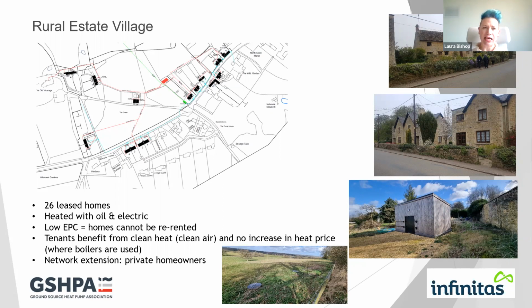So what the landowners decided to do was go down the ground source heat pump route. They would get renewable heat incentive, which they'll get for 20 years. This is an energy centre, which you can just see at the bottom right there. The energy centre has got 6 60-kilowatt NIBE heat pumps in there, so 360 kilowatts of capacity, coupled to a horizontal closed loop ground collector. That's in the field at the bottom there.